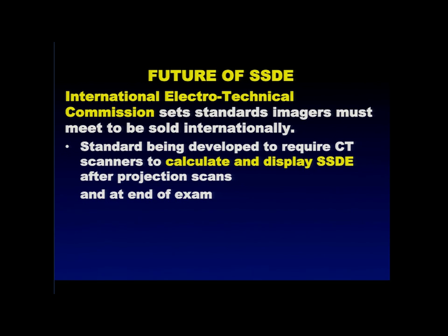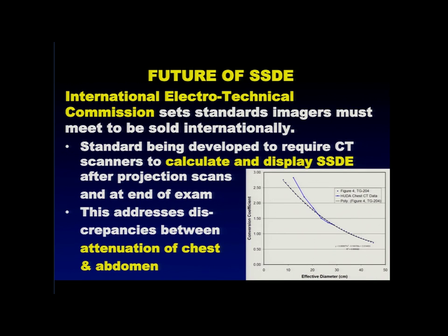It's going to display the SSDE after the projection scan and update it at the end of the exam so that the first displayed SSDE can be used, as we'll talk about at 11 o'clock, to manage the dose to your pediatric patients. The other beauty of having the manufacturers do the calculations is that they know how the body actually attenuated the X-ray beam during the projection scan. And they use that data to drive their automatic exposure control capability.